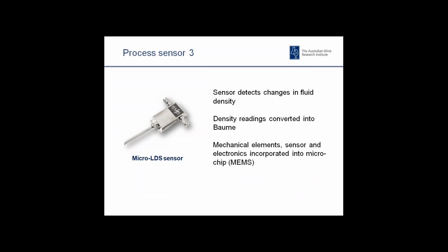Third sensor option is provided by Integrated Sensing Systems out of the USA. So the measurement principle here is very similar to the vibrating fork. We're looking at density measurements. Probably the key difference with this sensor is that it's a much smaller footprint. So all of the mechanical elements and the electronics are incorporated in what's called a MEMS, which is a microelectromechanical system that's similar to a microchip that carries all those useful elements. So much smaller footprint, not particularly process robust. It's certainly got lots of application for smaller scale and much cleaner environments.